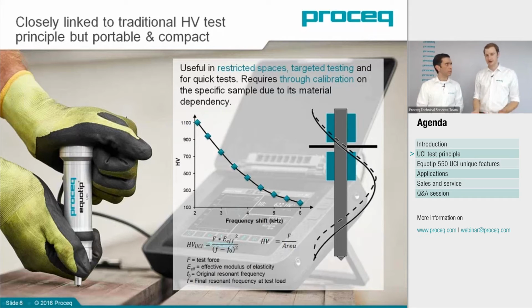In practical applications, if you want to overcome this and you have a different material than standard steel, what you can do is use the quick shift. Quick shift is a feature we are introducing on the Equotip 550, especially for UCI. This feature makes it very easy for the user to adjust the instrument for the material he wants to test. In a few steps, approximately 30 seconds, you can calibrate your instrument for your material.